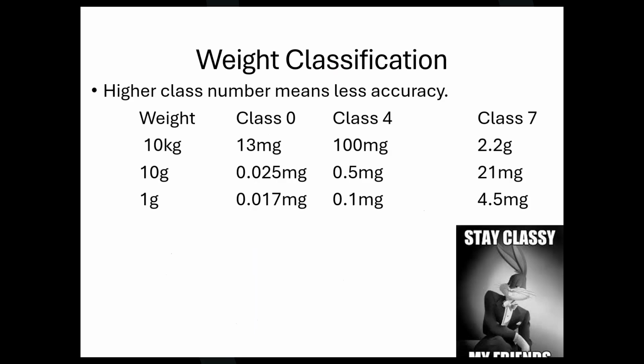So if we were going to pick a 10 kilogram class, what would we pick? Somebody take a guess. You could. 4 would be very accurate. What about this one here? Because we are a little better than 2 times more accurate. Remember, that thing will measure in 5-gram increments. So we are at 2 and 2.2 here. So, okay, that kind of works for us. We could do that. You could move up to a class 4 and that'd be very good. Nothing wrong with that.